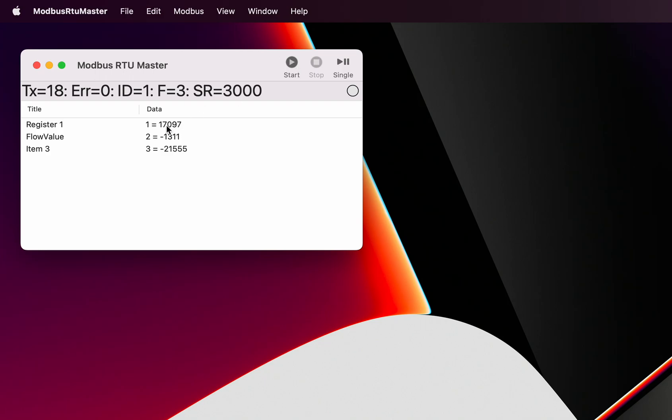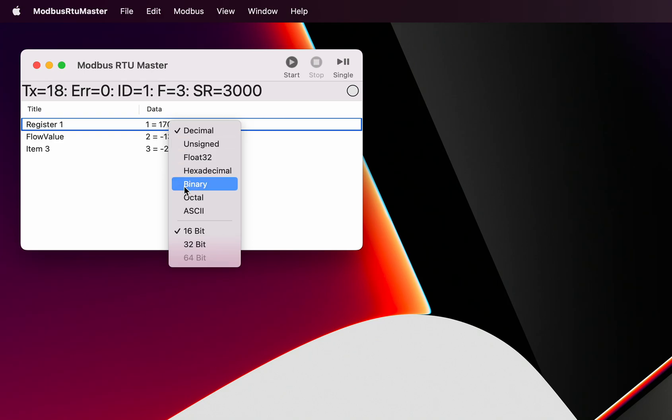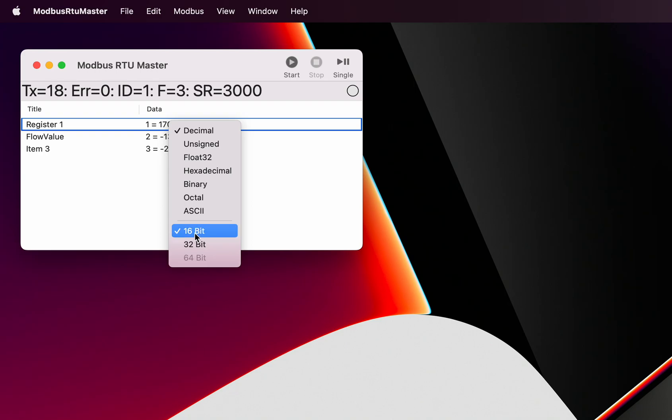That progress indicator will be showing until we've received the reply. A successful reply will give us an indication here of green. An unsuccessful reply will indicate red. You can see in here what we've got, the results of what we're receiving back from our slave. Now the information that we are receiving back can be read in this case as a one register decimal, but we've got many other ways of configuring it. In order to do that we just do an option or a right click. In that right click we can see the display format and there is a number of display formats available. We can also see that we have the option of reading or interpreting 16 bits, 32 bits, or 64 bits.